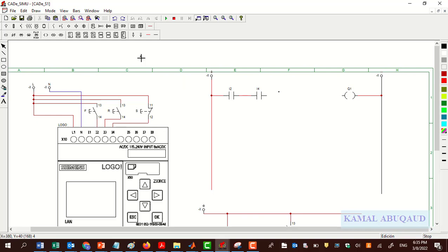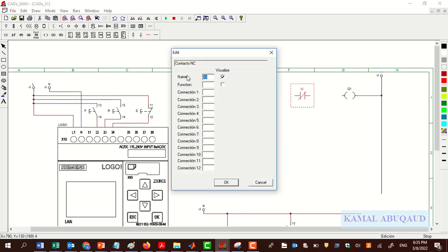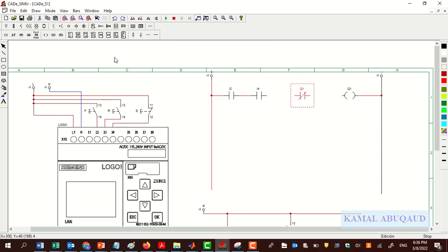Even though we did the physical interlock in the circuit, it is a good idea to have a software interlock as well. Software interlock means: when Q1 is on, I need to make sure Q2 cannot be turned on, and when Q2 is on, I need to make sure Q1 cannot be turned on. This can be done by adding a normally closed contact in series in our first rung.